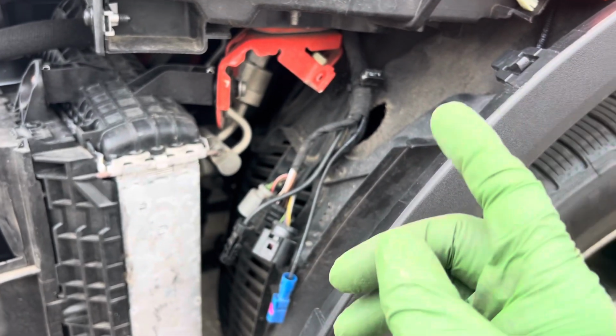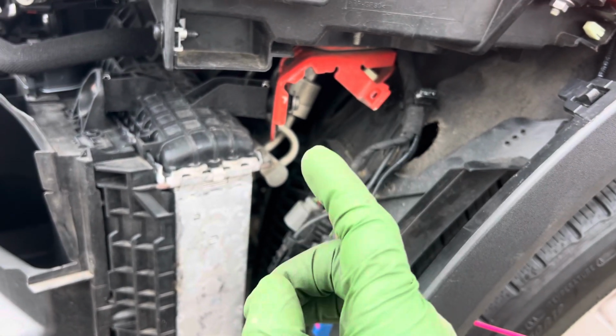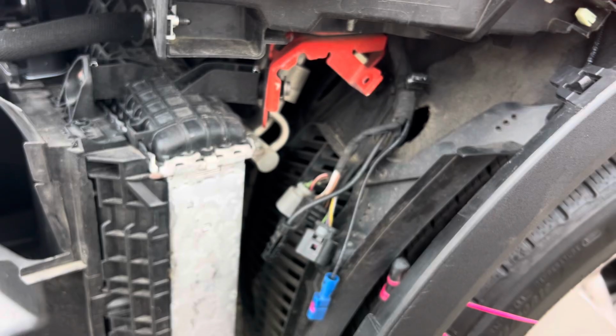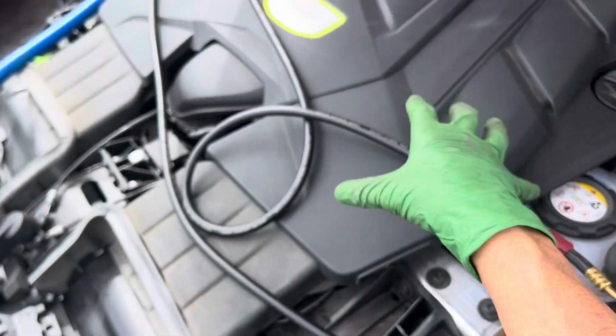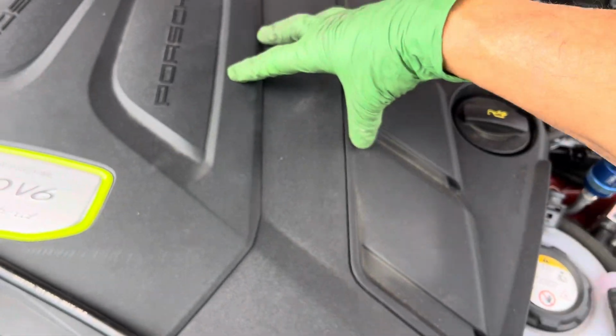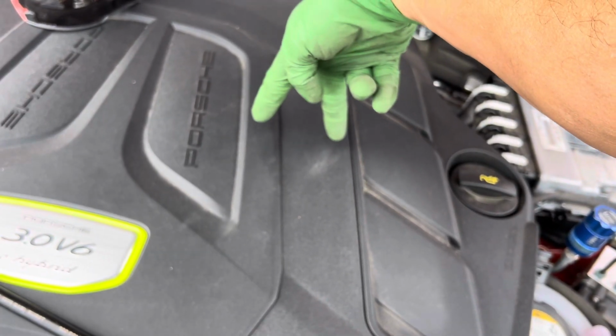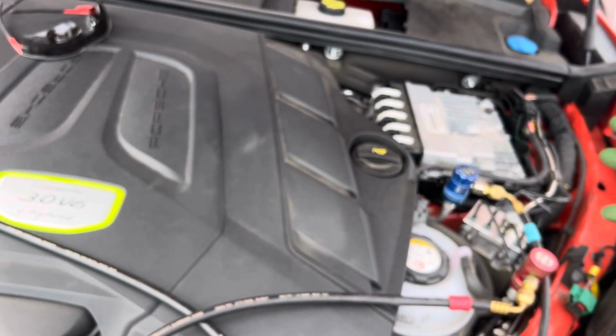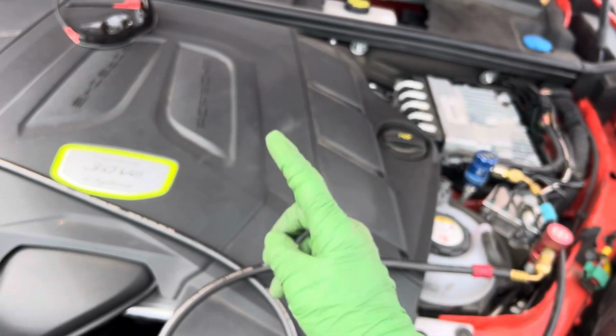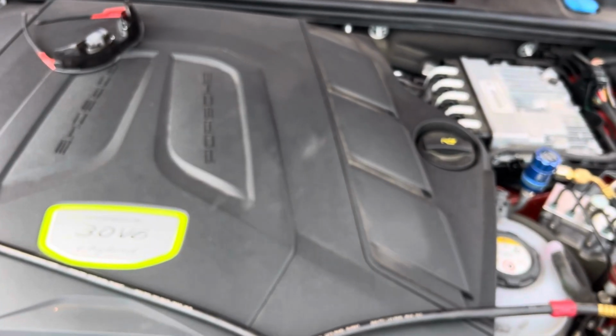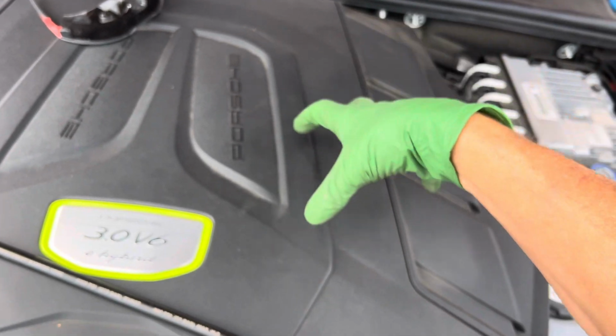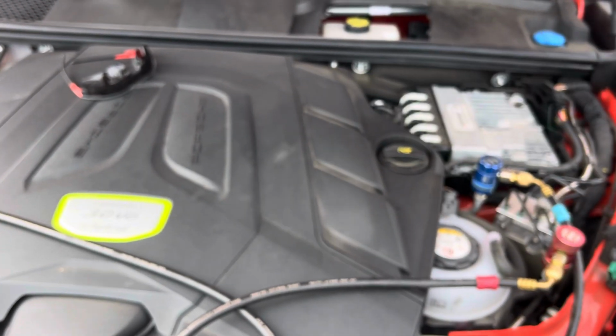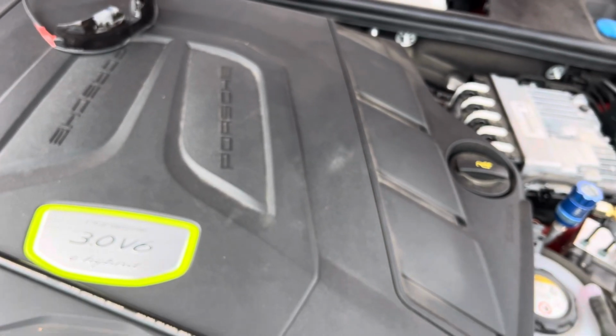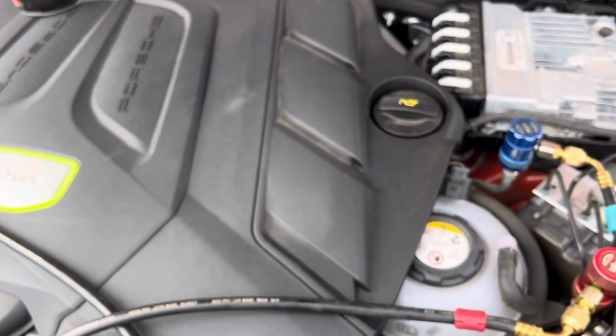I have to know how every circuit works, why something fails. If I see a certain particular car, like General Motors on some of the pickup trucks, they had the compressor up here, and you had the high side and low side fittings right on top of the compressors. And guys would hook up their recovery units, especially ones who didn't have training and didn't know they had to look and see that oil was being sucked out. It would literally suck oil right out of the compressor. Then they would charge it up with refrigerant, not put oil inside. One or two years later, the compressor dies from oil starvation. It doesn't happen right away.